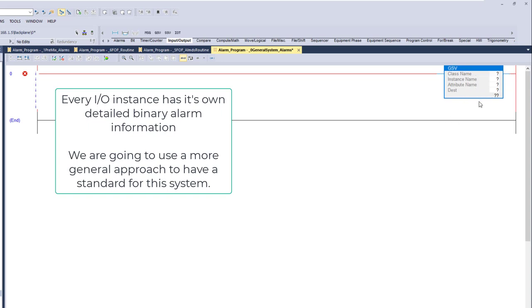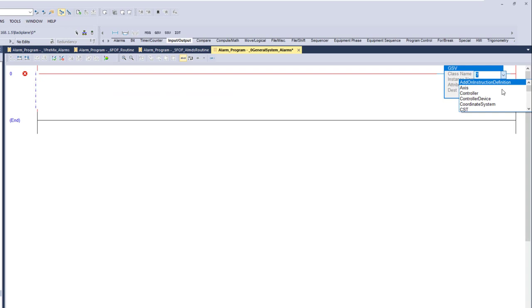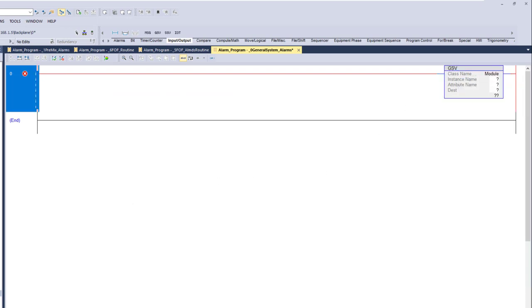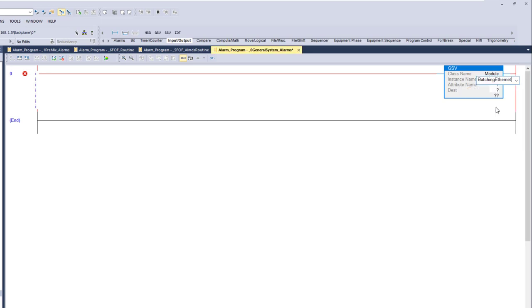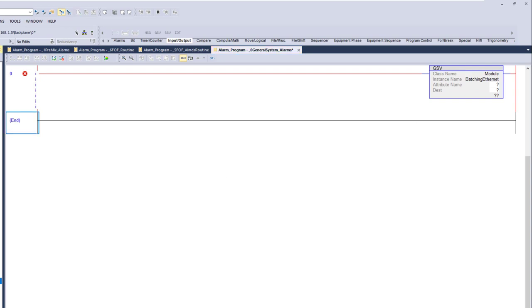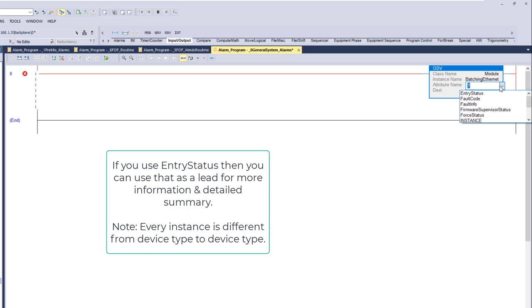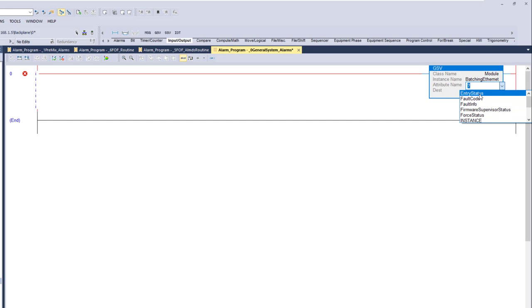For each instance, go into the class and pick 'Module' because we're going into our IO tree. We're pointing the GSV to the IO tree. Then pick the instance — I'm choosing the Ethernet card, the 1756-ENBT. It will show the name of the actual device, which we named 'Batching Ethernet.' Then get the actual attribute. You can get the entry status and compare it against different codes and binary setups to pull out different information.